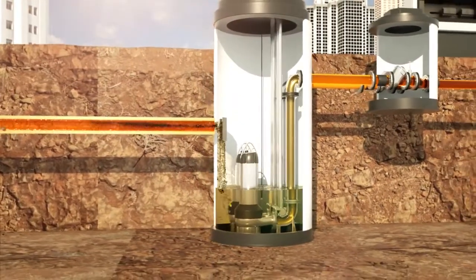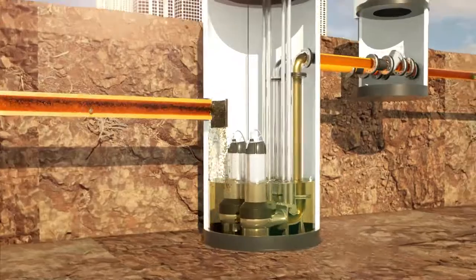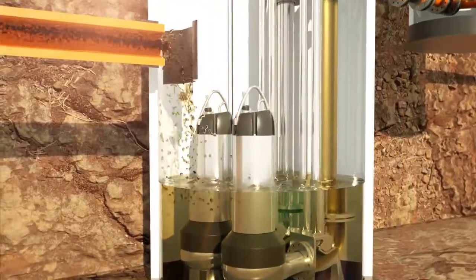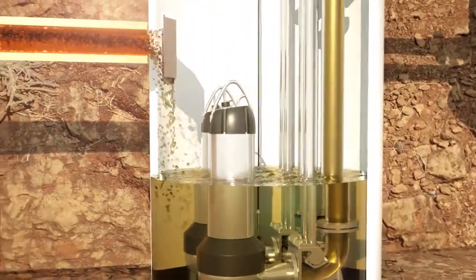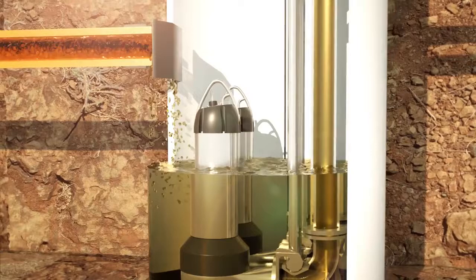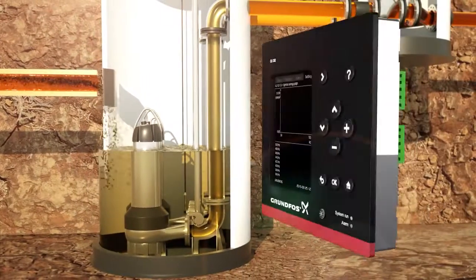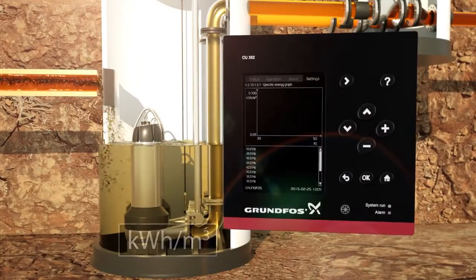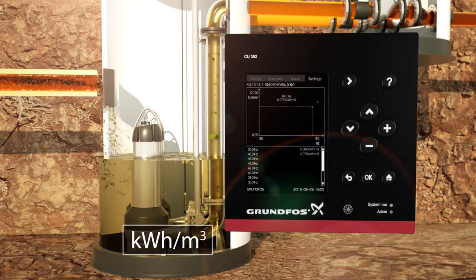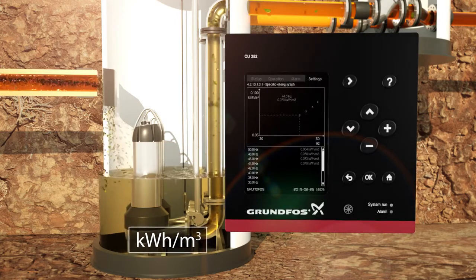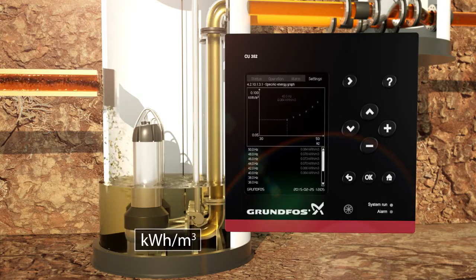By implementation of the dedicated controller, along with the frequency drive, pumps can now be run with minimum possible energy consumption and enough capacity to handle incoming flow. Controls continuously learn and adapt to duty conditions in the specific pumping system. The controller immediately adapts pump speed in response to data from the frequency drive and a flow meter.